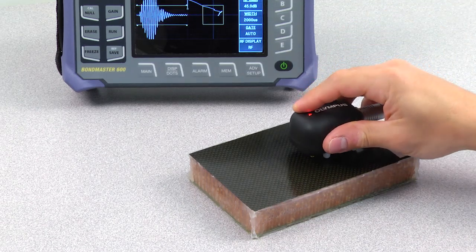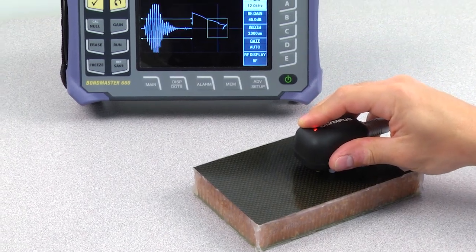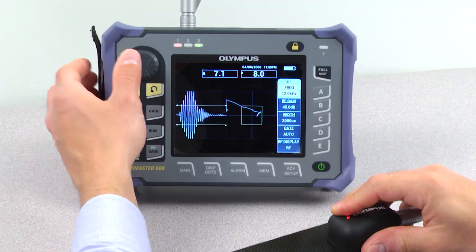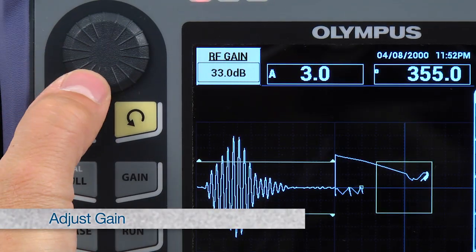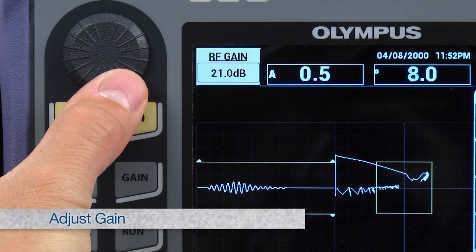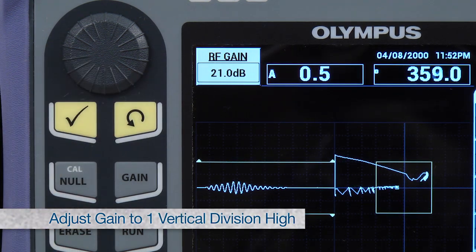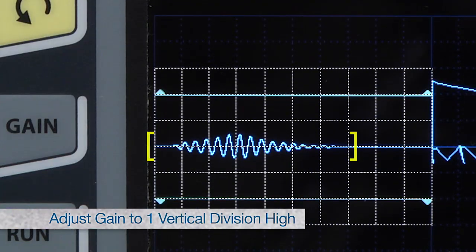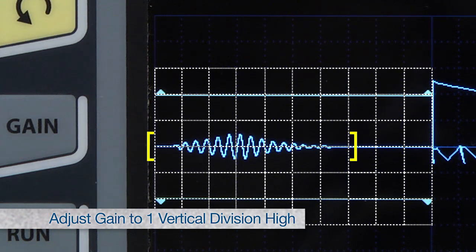Put the probe on an area free of defects on the standard and maintain the probe tips over the area. Press the gain key. Adjust the gain so that the RF signal does not exceed two vertical divisions high. A total of one division high is generally a good start.